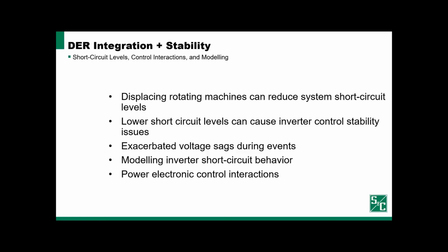As we've discussed to a significant extent already, displacing rotating machines can reduce the system short circuit levels. This impacts our protection, but it also impacts system stability. Reduced system short circuit levels can be a challenge for inverter-based resources themselves, which often require a stiff system for their control loops to work properly. The reduced short circuit levels can also exacerbate voltage sags that we experience during events. We can have deeper voltage sags in a weaker system.